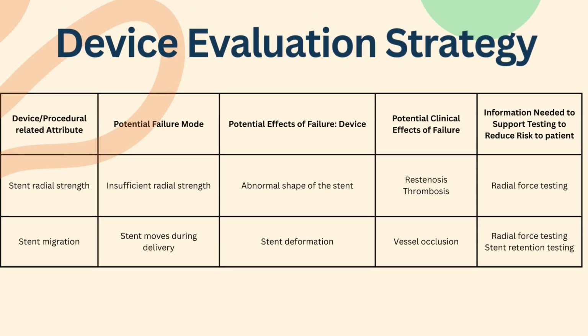And going on, we could also have problems with insufficient radial strength of the stent. This would make the shape of the stent abnormal and again lead to restenosis and thrombosis. How we could avoid this is by doing radial force testing so that we could avoid restenosis and thrombosis. The last issue that we thought about was stent migration. It basically moves during the delivery, and this could lead to the stent being deformed, and that could cause vessel occlusion. So what we would have to do is, again, radial force testing and also stent retention testing as well.